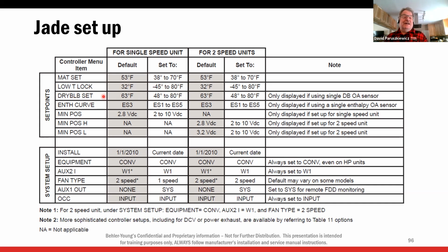Dry bulb setting. If you're doing an economizer in Michigan, don't use dry bulb. That's an outside temperature sensor, not enthalpy. Don't even bother. Enthalpy curve, again, that's that chart we looked at, ES3. You probably should never have to adjust this because it does cover that whole range. Like we used to have to go to A, B, C, D, you shouldn't adjust this. Minimum position. Now on a single stage unit, I have a single minimum position. This is a 2 to 10 volt signal going to this damper motor. So 2.8 volts DC, that's the signal it's sending out. That's the factory set minimum position.